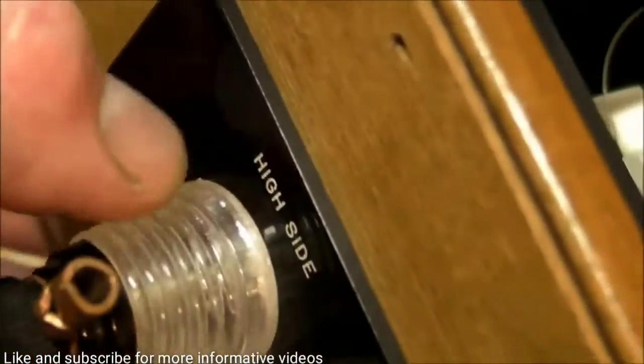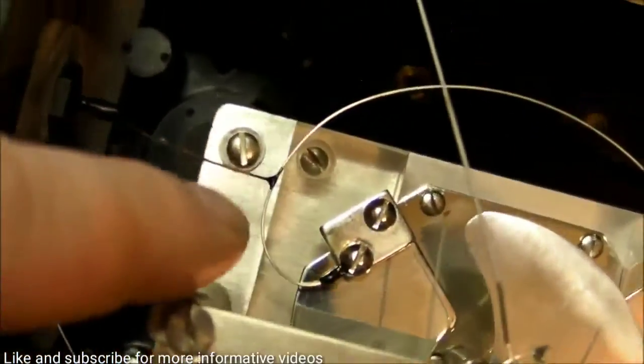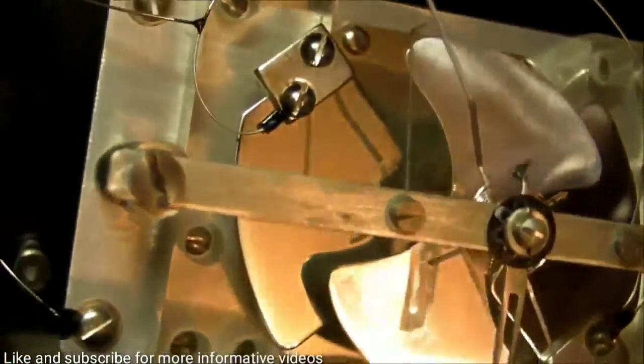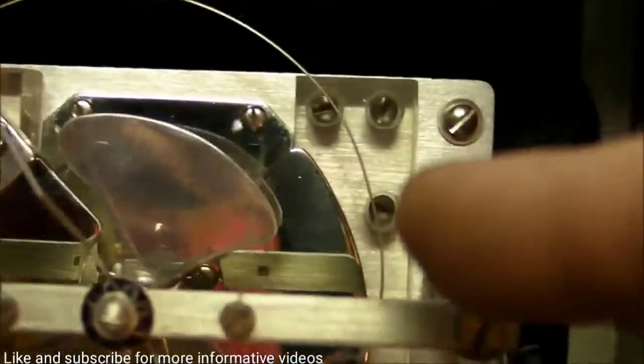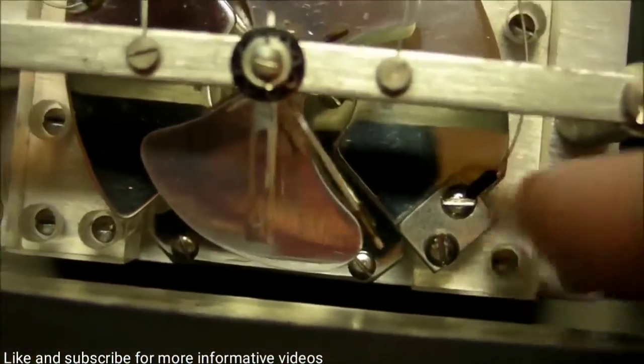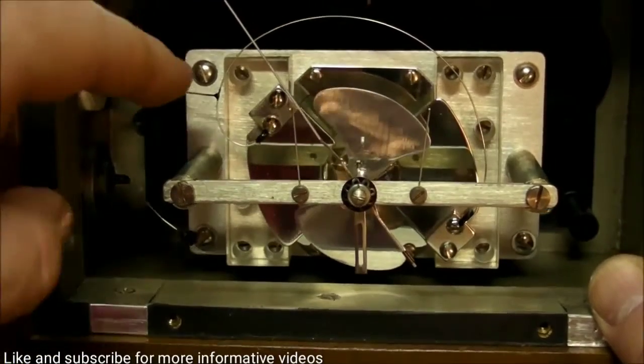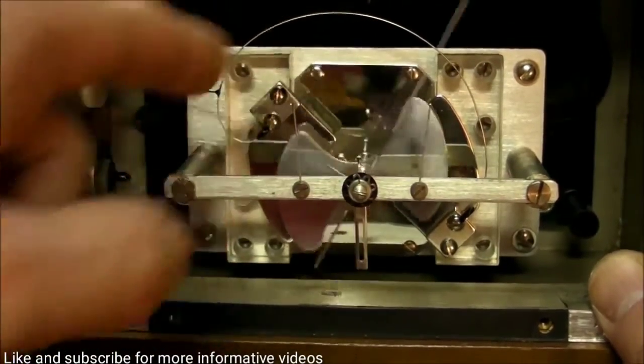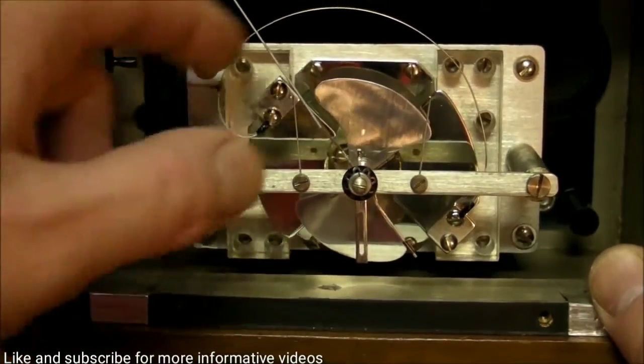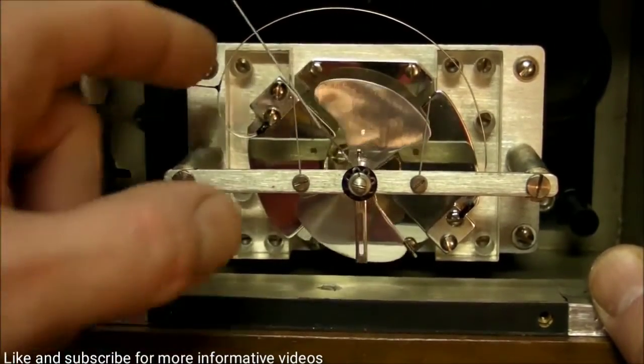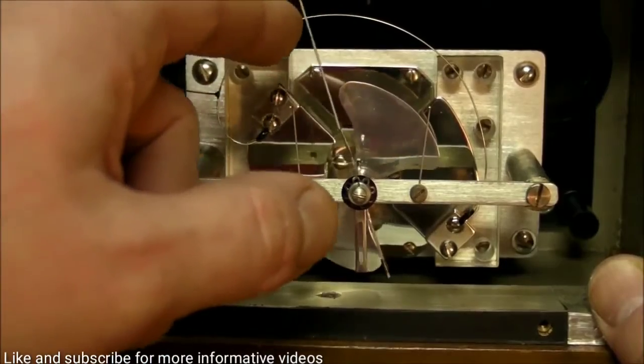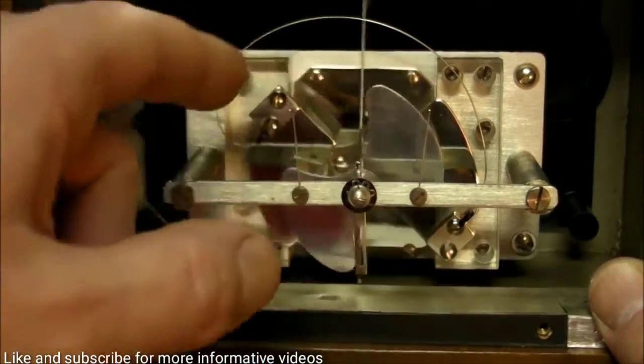Now the terminal that does get energized, or at least should get energized, is the high side here on this clear plastic insulator, and that comes out through the box and hooked up to the 2 stationary plates just beneath the moving plate. So there's one plate right there, and then it's got this nice looping wire going all the way around here to right there. So if you haven't guessed it already, this moving ground plate gets attracted to the stationary high voltage plates completely electrostatically.